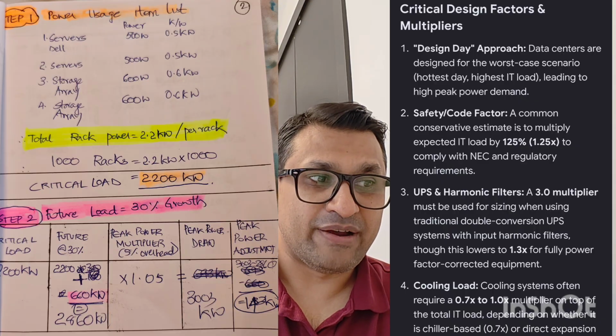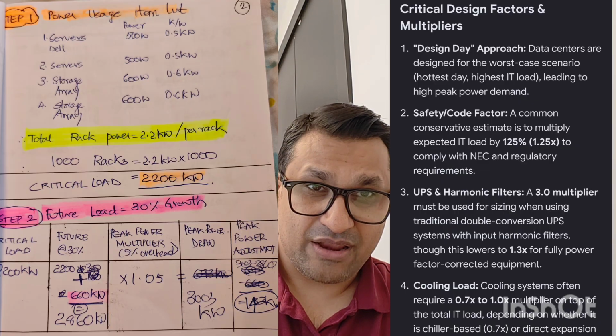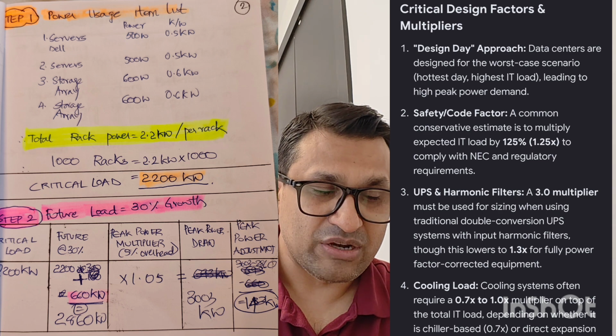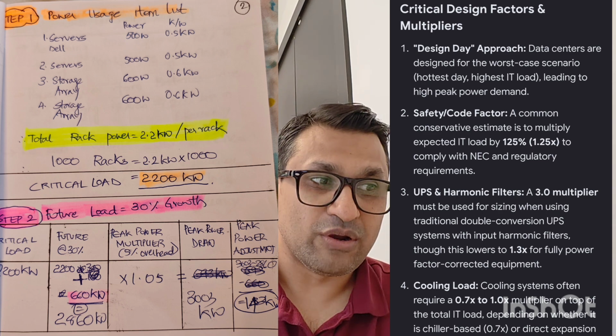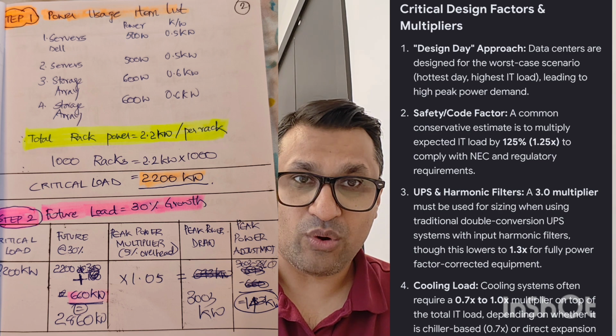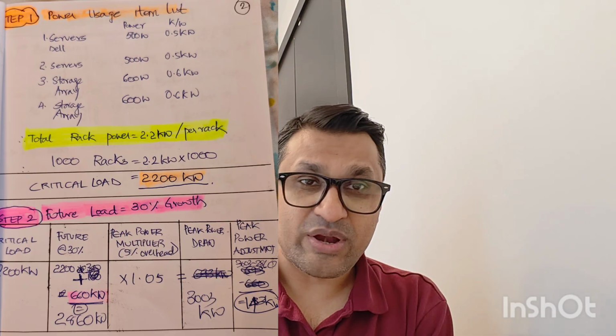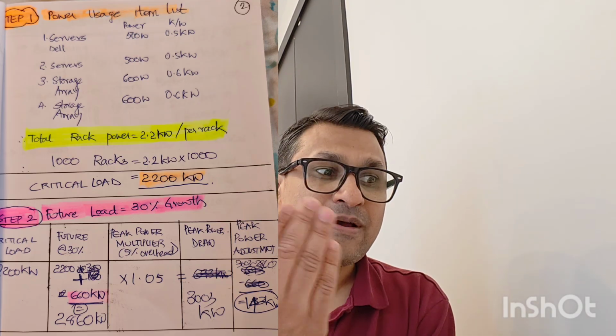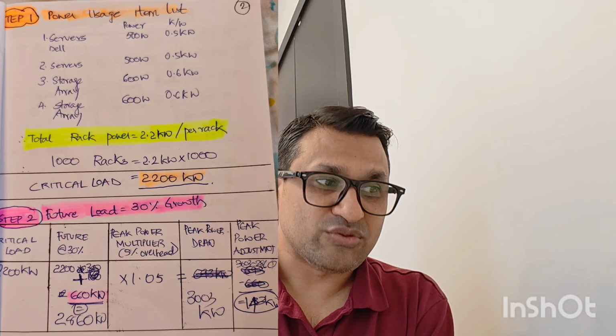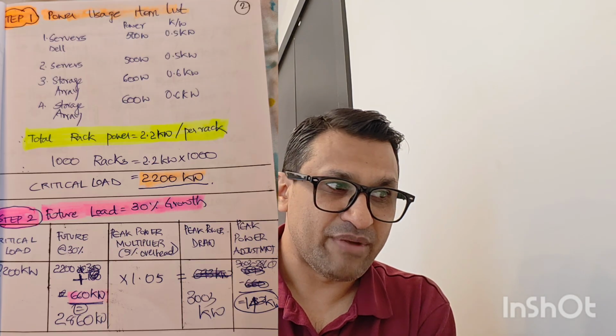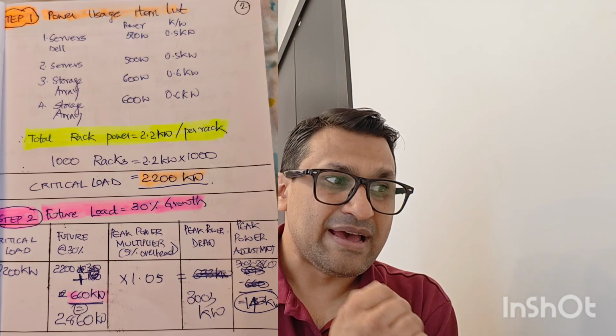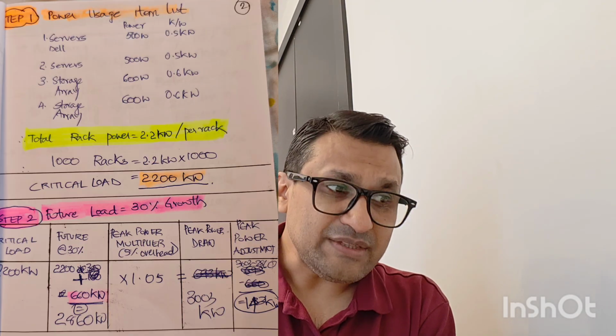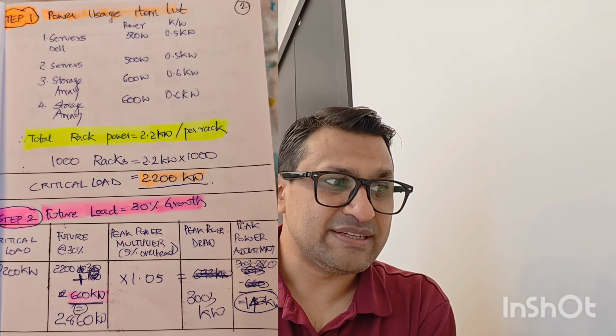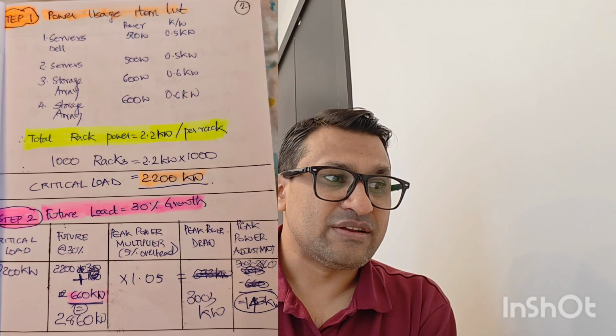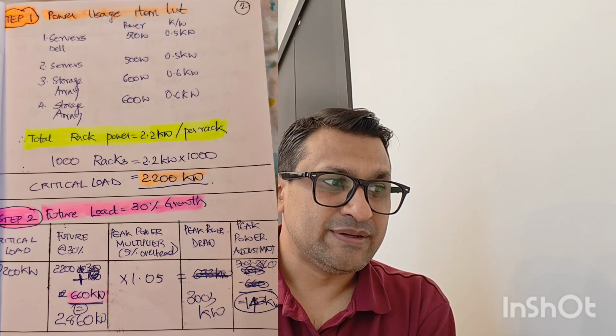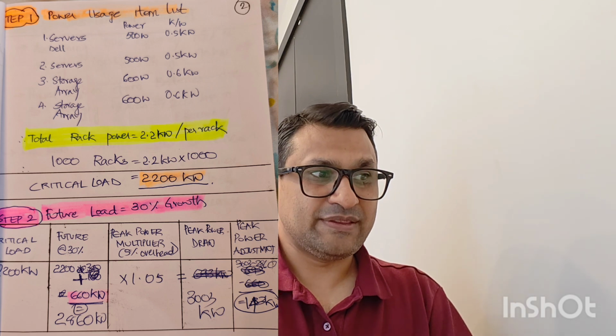If you have a peak power multiplier with 5% overhead, remember, if you give 5%, it's 1.05. You multiply it. If it's 10% overhead, you give 1.1. So you're giving 5% overhead, 1.05. And after multiplying 2860 times 1.05, you have 3003 kilowatt or 3.0 megawatt. That's the peak power drawn. And the peak power adjustment is 3003 minus 2860. That's 143 kilowatt. Okay, that's the peak power adjustment.